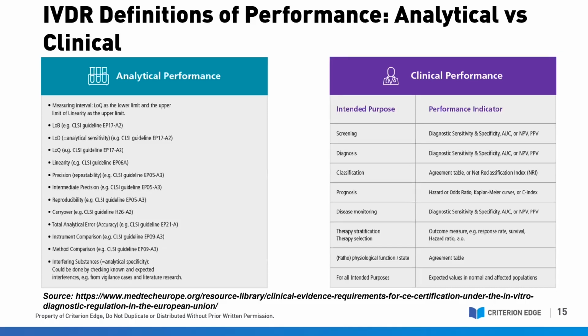The sensitivity one day after a missed period is going to be much different than 10 days or 20 days. So pay attention to timeframes, pay attention to particular patient populations where you may expect that the sensitivity could be altered or different. And pay attention to which analytical and clinical performance measures you want to capture. Generally speaking, the indicators of analytical performance are pretty similar or even identical across many IVDs, whereas indicators of clinical performance will vary, but they depend very strongly on that intended purpose. So if you've clearly defined your intended purpose, you have a pretty good idea of what clinical performance objectives to be on the lookout for.